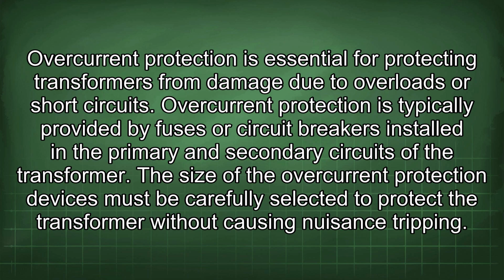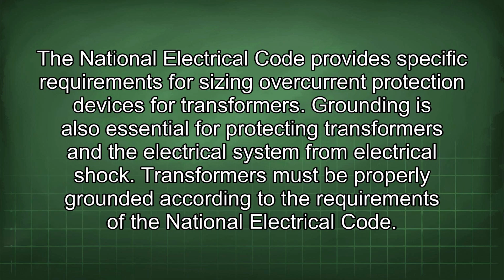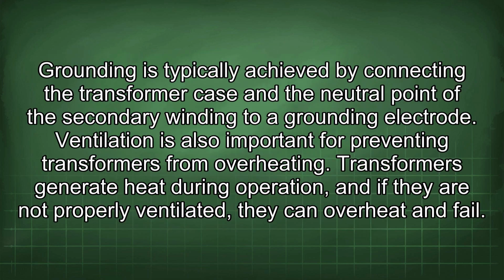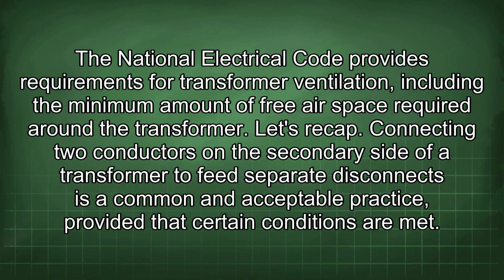The size of the overcurrent protection devices must be carefully selected to protect the transformer without causing nuisance tripping. The National Electrical Code provides specific requirements for sizing overcurrent protection devices for transformers. Grounding is also essential for protecting transformers and the electrical system from electrical shock. Transformers must be properly grounded according to the requirements of the National Electrical Code. Grounding is typically achieved by connecting the transformer case and the neutral point of the secondary winding to a grounding electrode. Ventilation is also important for preventing transformers from overheating. Transformers generate heat during operation, and if they are not properly ventilated, they can overheat and fail. The National Electrical Code provides requirements for transformer ventilation, including the minimum amount of free airspace required around the transformer.